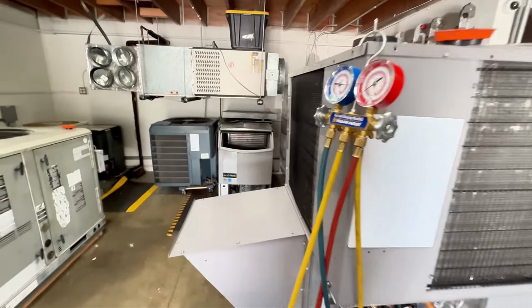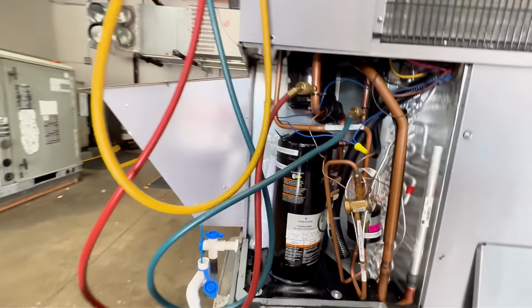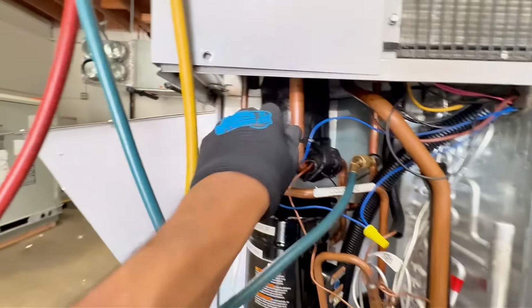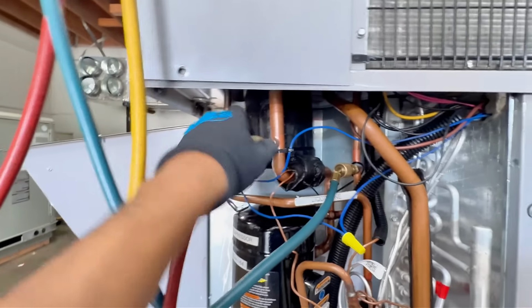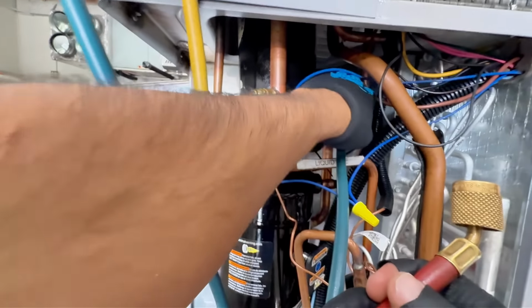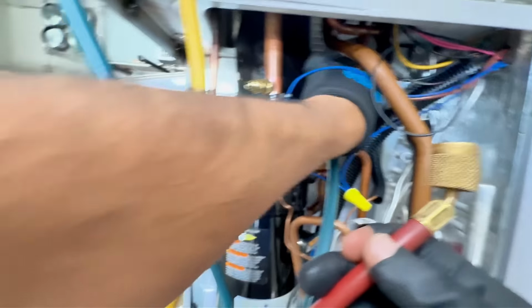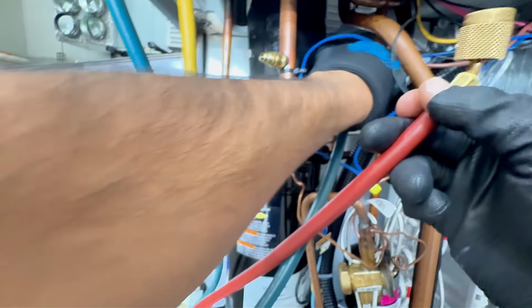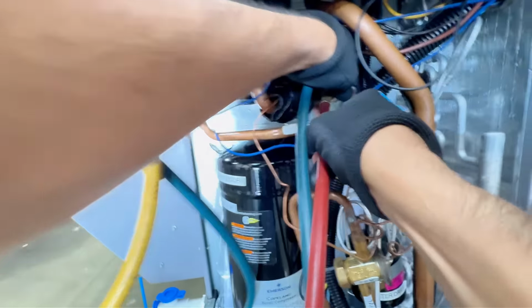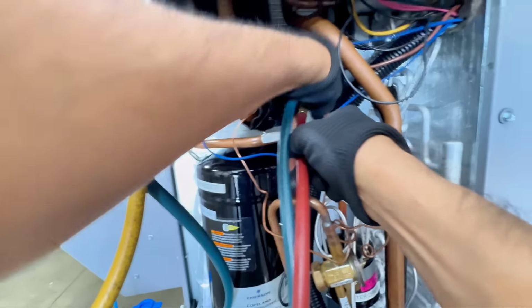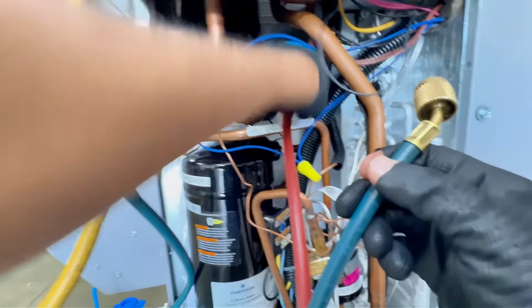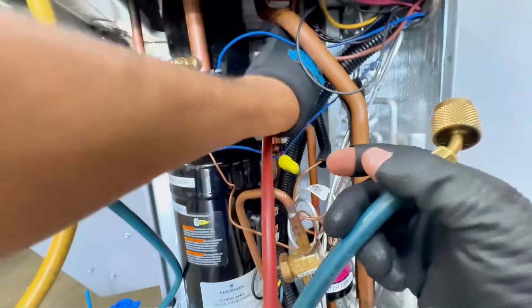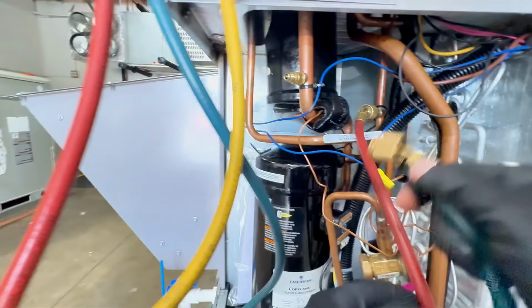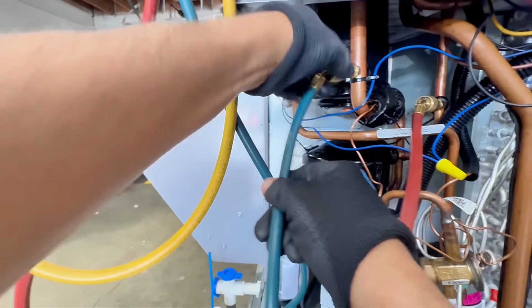So, let's see what's going on right here. Oh my goodness, what's going on? Sorry guys, rookie mistake. I'm gonna pretend you guys didn't see that. I'm looking at my gauges. I'm like, what is going on? The red one, of course, is the high side, goes to my discharge line. That's okay, that happens. As long as you recognize that it happened, otherwise you'd be there for some time trying to find out why your low side pressure is high and your high side pressure is low. But the red hose goes to your high side, my blue one goes to your suction line, right?